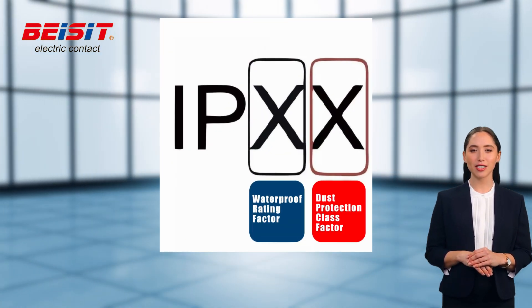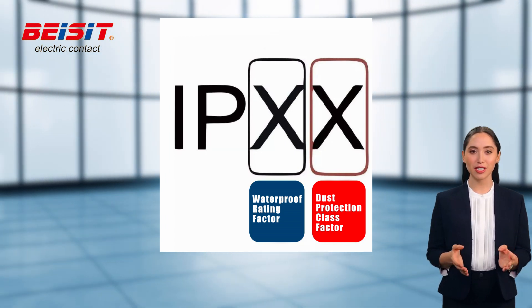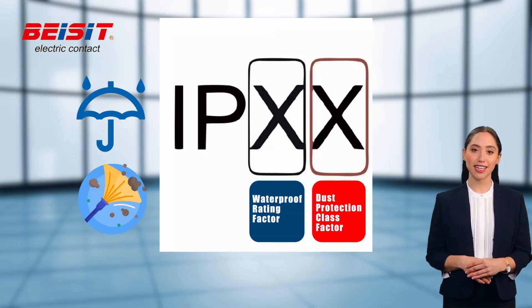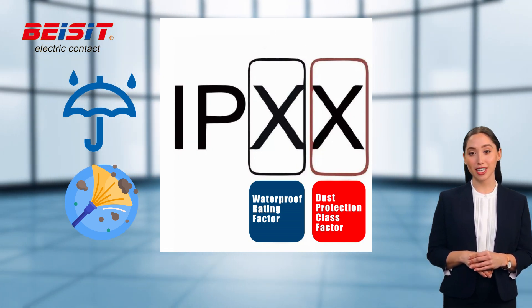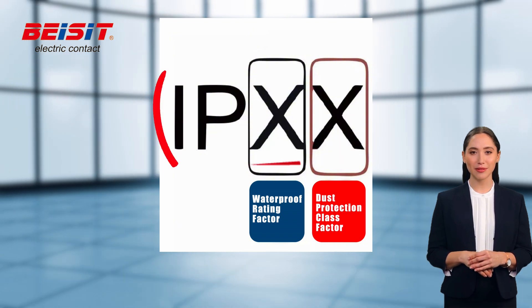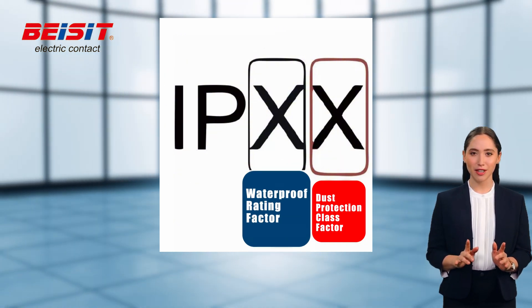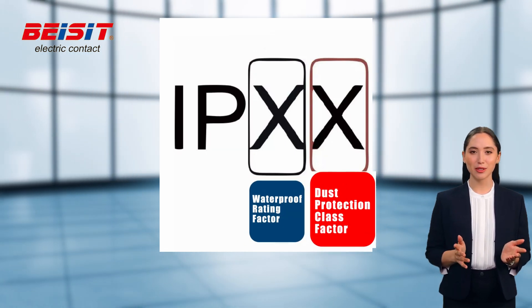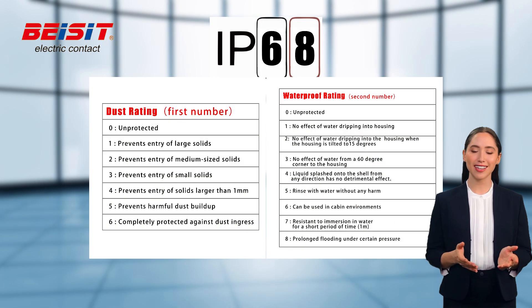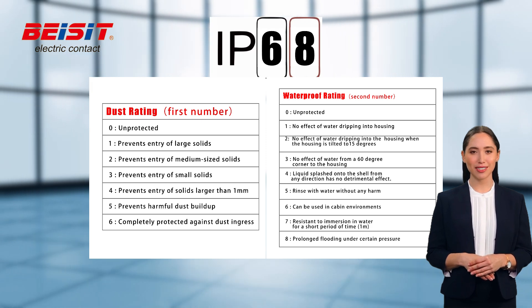The IP-grade certification, according to the standards issued by the International Electrotechnical Commission (IEC), ensures the cable glands' resistance to dust and water, providing the necessary protection for cables and wires. The IP rating is usually composed of 'IP' followed by two numbers. The first number indicates the dust resistance level and the second indicates the water resistance level. For example, IP68 means the device has the highest level of dust and water resistance.